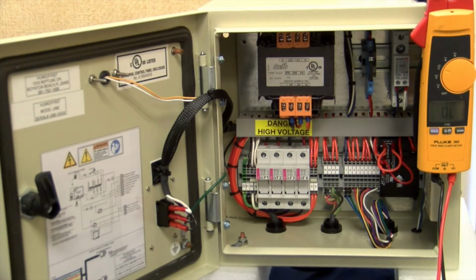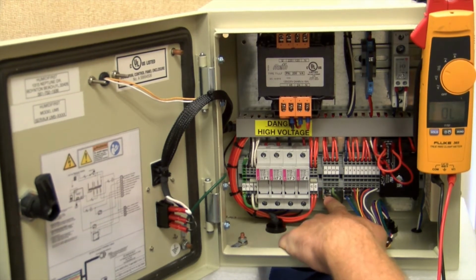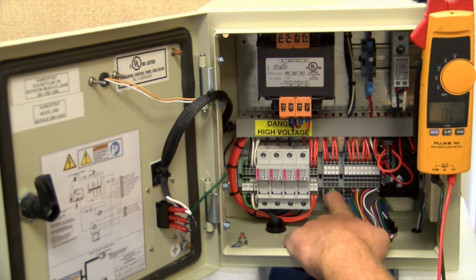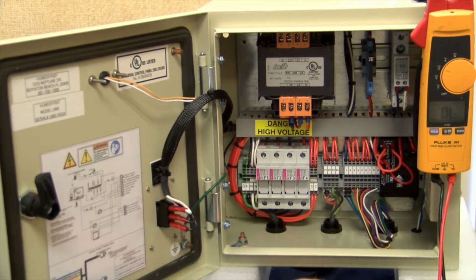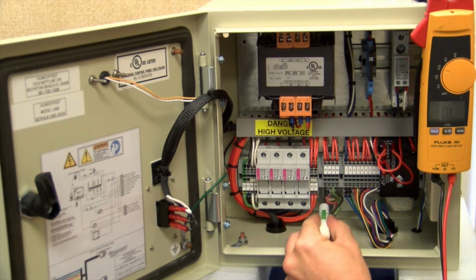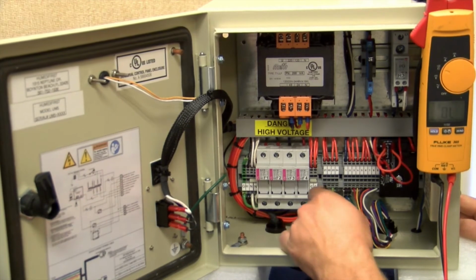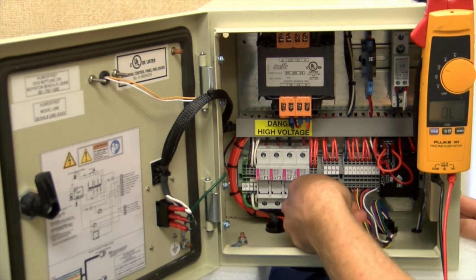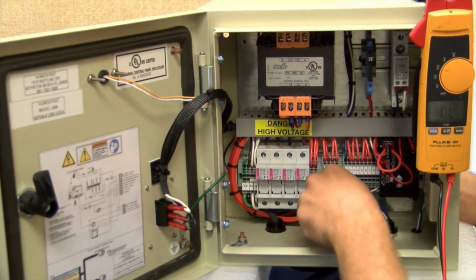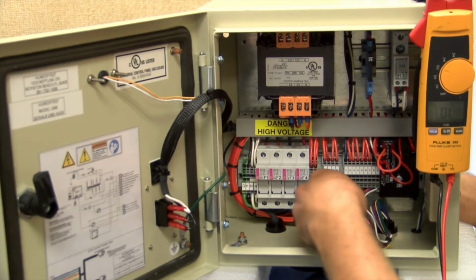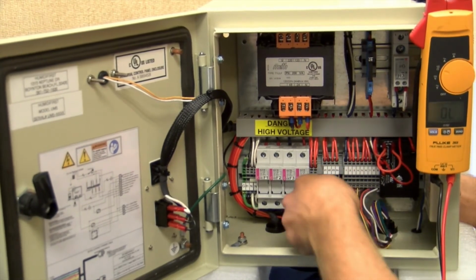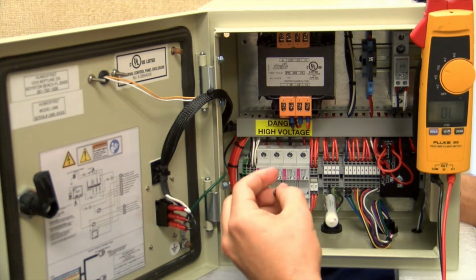We are now going to check your surge arrestors. You have two surge arrestors on this unit at 21, 22, and 1 and 2. Surge arrestors work the exact opposite of a fuse. If you tone across it and don't get continuity, then it's good. If you tone across it and get continuity, it is bad. To check it, simply remove the surge arrestor by taking a Tech screwdriver or a small screwdriver with a small tip, place it in the slot directly above the surge arrestor, push it in, and it will dislodge the surge arrestor. You'll have to do it one for each side. And the surge arrestor will come out.